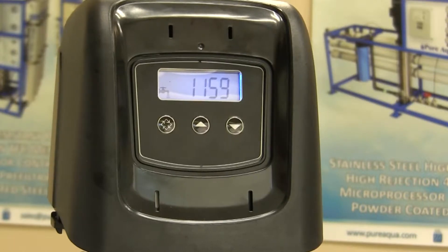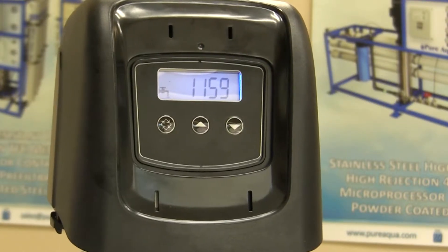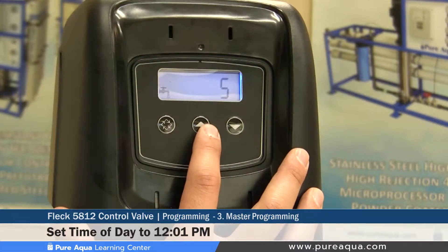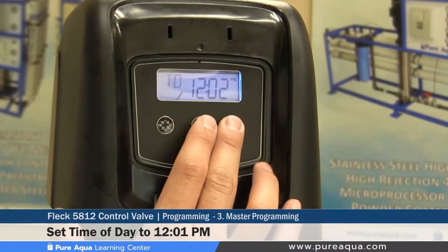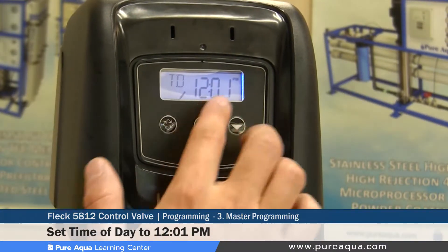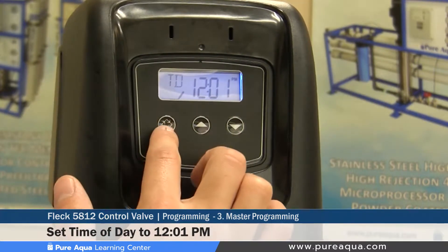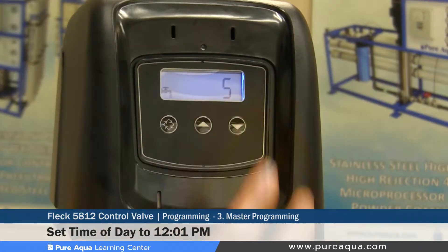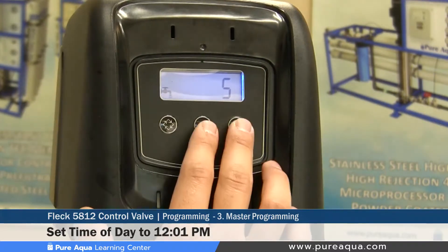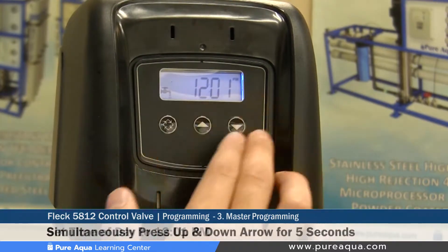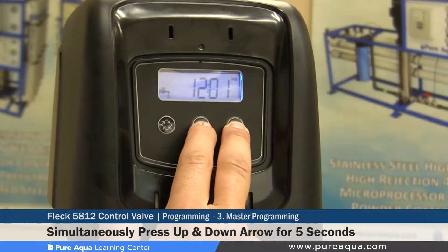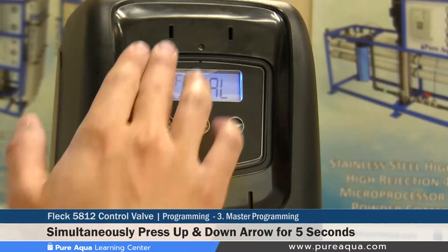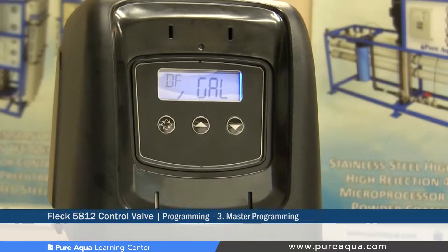Now we will discuss the master programming mode, the third section of our programming tutorial. Step one is to access the master programming mode. To do so, you must set the time of day to 12:01 PM and press the extra cycle button. Regardless of your valve's current time, set it to 12:01 PM, then hold the up and down arrows simultaneously for about 5 seconds. After 5 seconds, the first set point will be the DF.